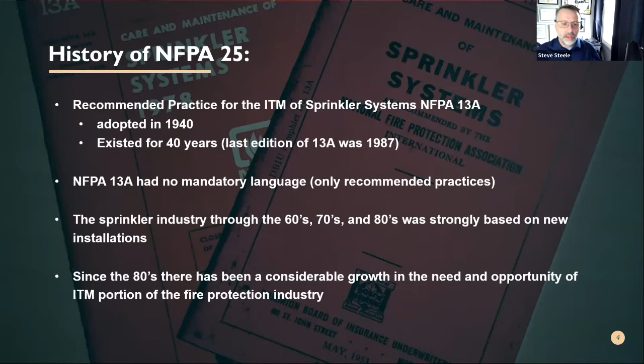So prior to the creation of 25, what they did find out, and probably some of you may be aware of, is what leads to system failure on fire protection, especially water-based sprinkler systems. What is the number one cause? It's very well documented, and you can find out that most of those failures were not only from improperly maintained systems, but from routine things such as not following up, when a system has been serviced, to verify that the valve has been returned to the open position or fully open.